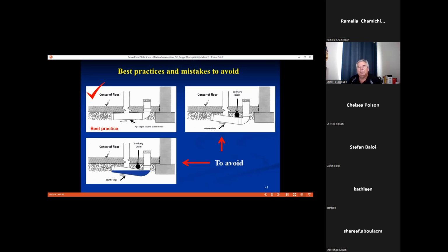On a typical day, we're taking out the equivalent of 1 to 2 gallons of water a day in terms of humidity. So there's a lot of water that runs back to the soil from our system. And if you have a proper slope going to the center, then if you had a solid pipe here, that water would drain out at the end of the pipe. If you have a cap on it, then it simply fills the pipe with water.